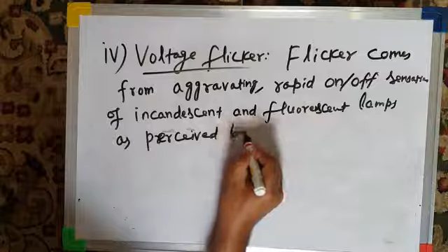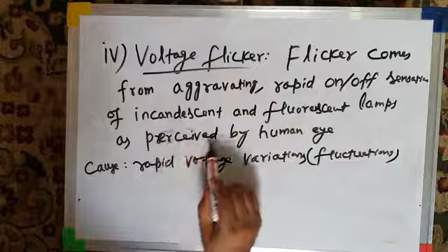Okay, and these flickers come from voltage variations, rapid voltage variations. And what are these rapid voltage variations? They are nothing but fluctuations. We have just a few moments back studied that rapid voltage variations are fluctuations. Whenever there are rapid voltage variations because of any of the causes, like rapidly cycling loads, electric arc lamp, electric arc furnace, electric arc welding equipment, or adjustable speed drive with inadequate DC link filtering connected to a weak AC system, one of them may cause rapid voltage variations, and these voltage fluctuations result in aggravating rapid on-off sensation of incandescent and fluorescent lamps as perceived by human eye.